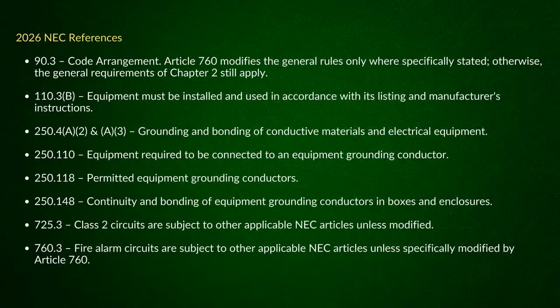And they also had another one in there that wasn't new, it's been in there, where it talked about electrically continuous metal raceways and listed auxiliary gutters. And I would say that's not considered an electrically continuous metal raceway. I would consider that a surface metal raceway, but it has to be the type of raceway that has been listed for grounding.